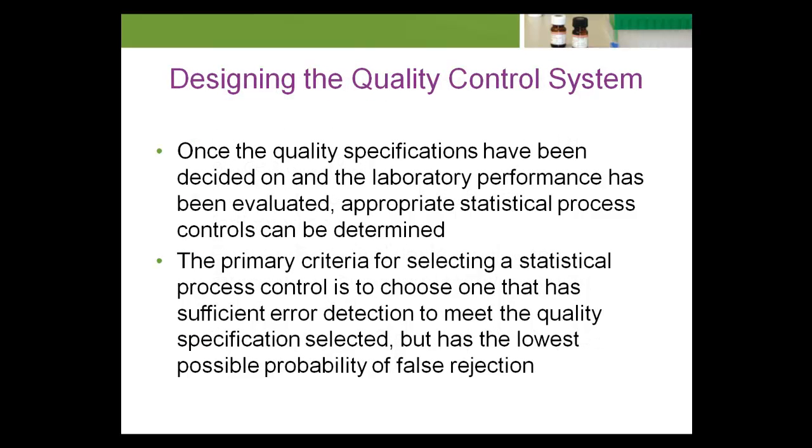In most QC rules, there is a trade-off between error detection power and false rejection rate. The error detection power is the probability of a QC rule of detecting an error. However, the false rejection rate is the probability that the rule will indicate a problem when none exists. The essence of good quality control design is to select QC rules that have sufficient error detection power to detect critical errors but the lowest possible false rejection rate.